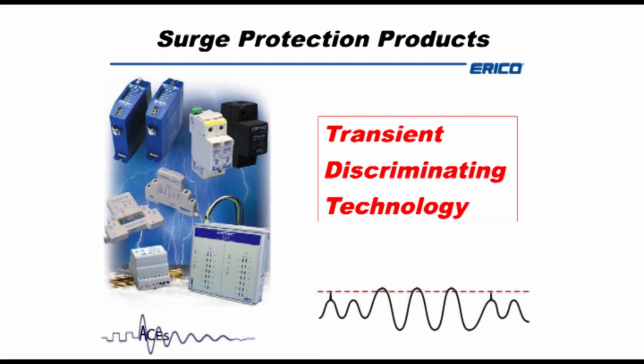What we discovered in the early to mid 90s, when the surge protection industry was barely a decade old, was that we were starting to see switchboard fires caused mostly by premature aging of those metal oxide varistors. They're kind of like a decent sized PN junction, and over time they degrade. When they degrade, they quite often fail to a near short or short circuit, interconnecting wires get hot, insulation catches fire, and you get a switchboard fire.